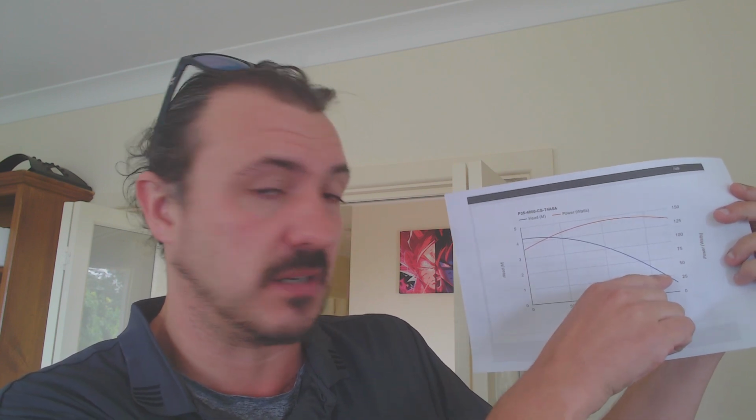If I then increase to 50 millimetre, my head comes down to 1.37 or 1.67. Even at 1.67, 1.67 is right on 150 litres a minute. At 1.37, I'm getting a little bit more than 150 litres a minute, and that's where I put the valve on the outlet that I've got in my friction loss sizing. That's where I would use that to control that flow. If you've got a DC pump, you can use it to control the flow backwards as well.